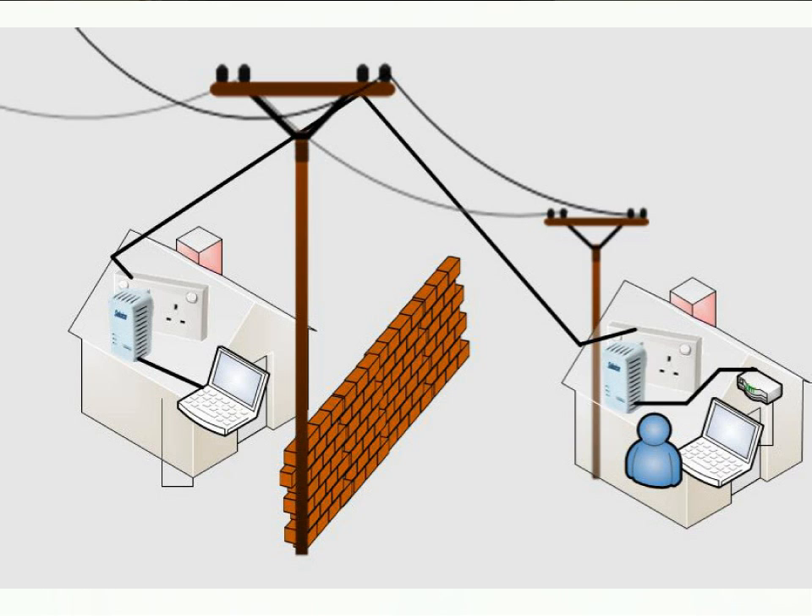Powerline Networking Technology, Powerline Telecommunications — the manufacturers state that the signal generated by the PLT devices does not make it past the electricity meter. This video proves otherwise. Without getting too complicated, the properties in which both laptops were sited were fed by electricity on the same phase. This video has proven that it certainly travels from the ring main of one house, through service cable to an overhead connection, back down an adjacent service cable to an adjacent house.